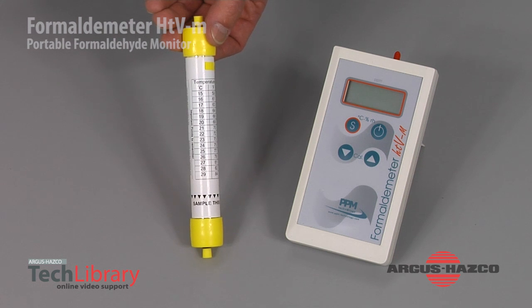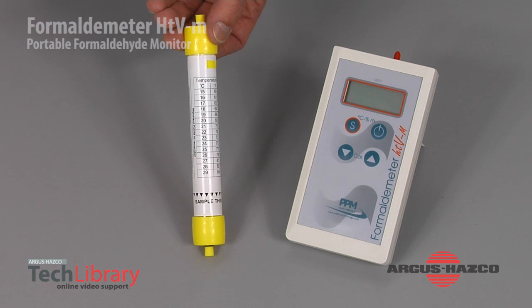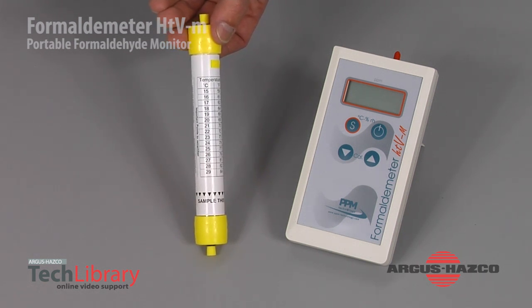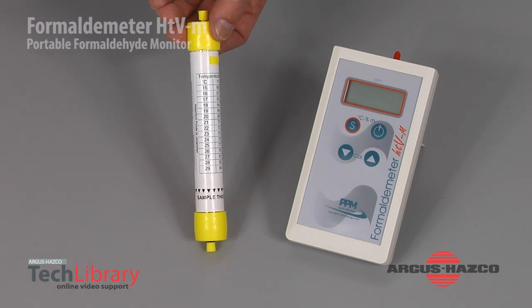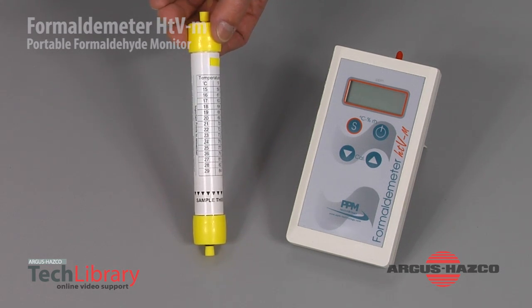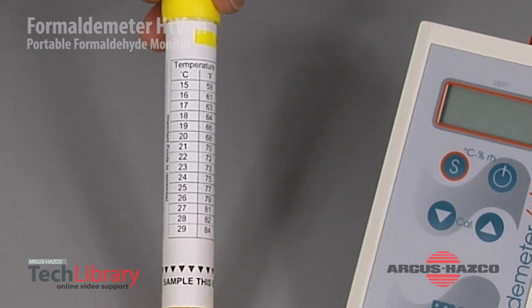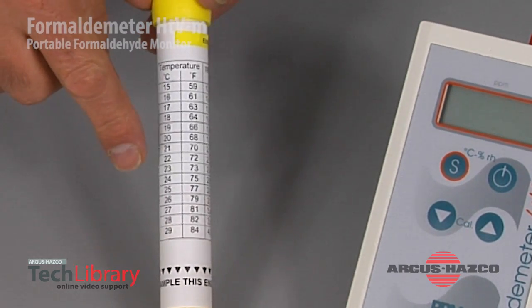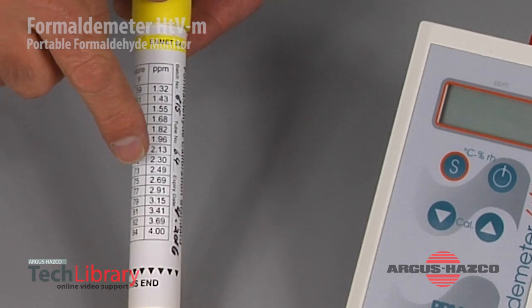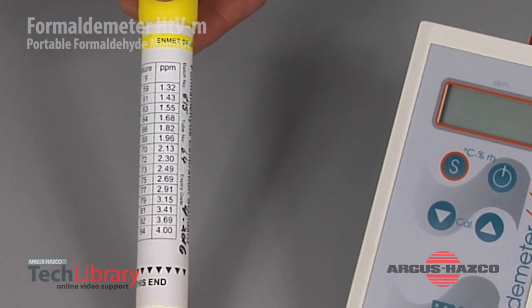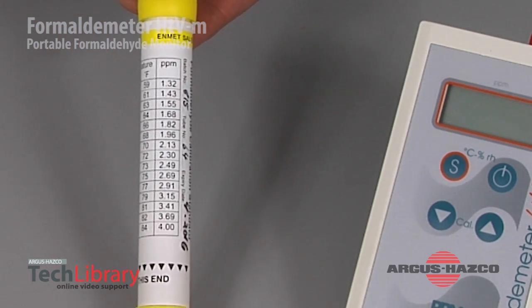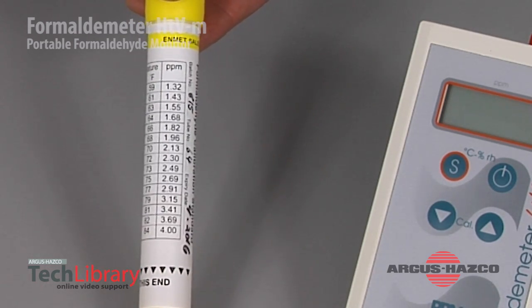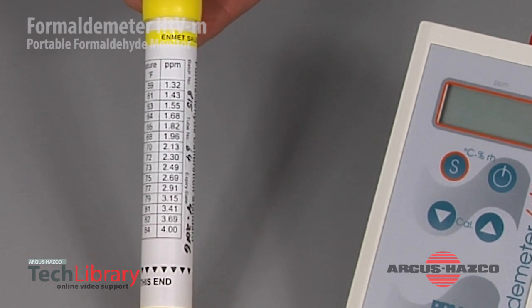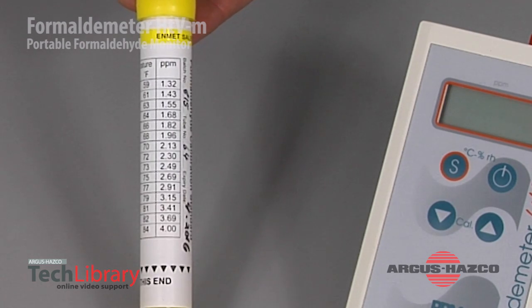So from our temperature readings of 22.5, we need to round up to 23. Now if it was below 0.5, say 22.4, we'll need to adjust it down. If we're adjusting it to the temperature of 23, we need to look at our chart, and it tells me in terms of ppm, relative response factor, I have to adjust the unit to 2.49. I will now show you how to calibrate the instrument accordingly.